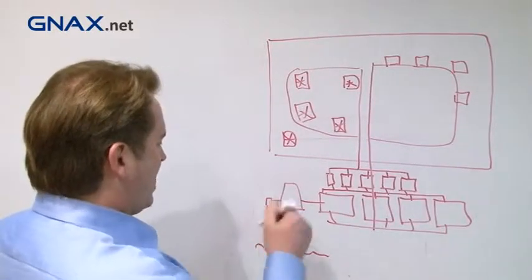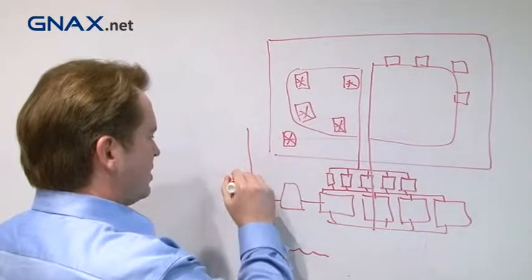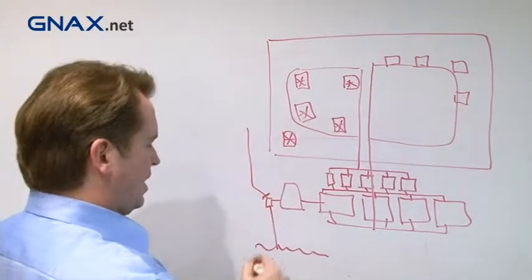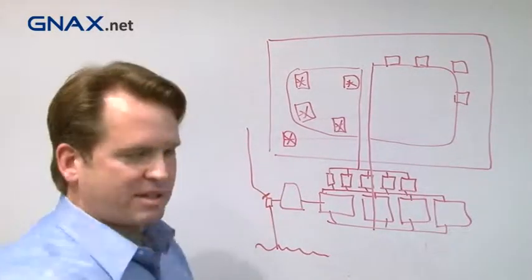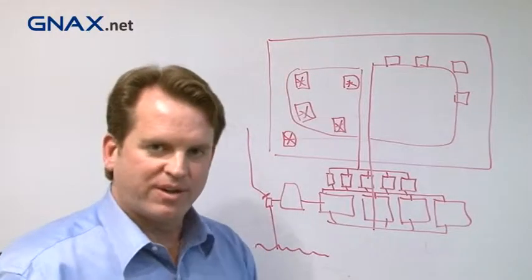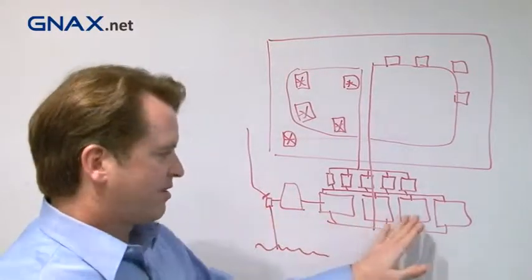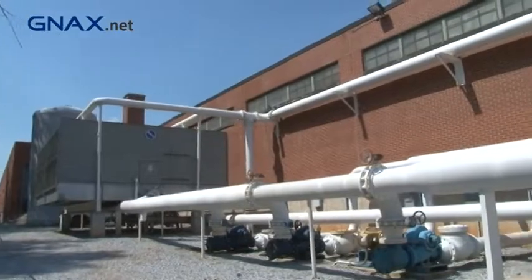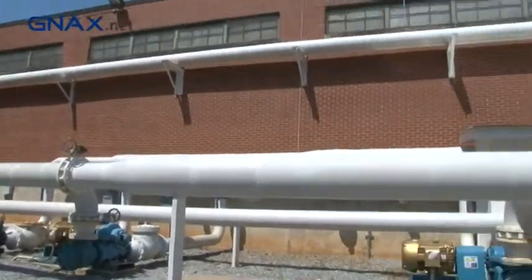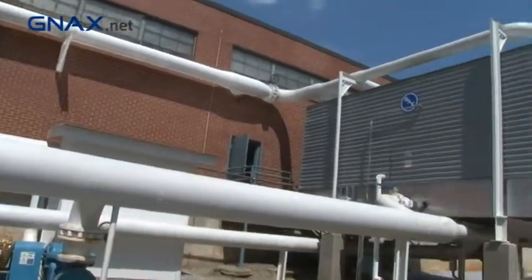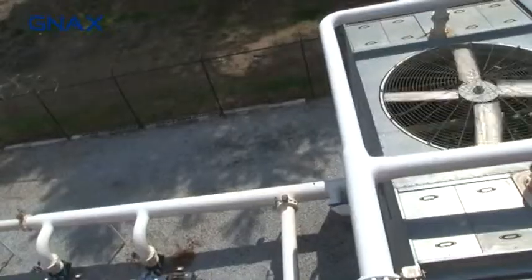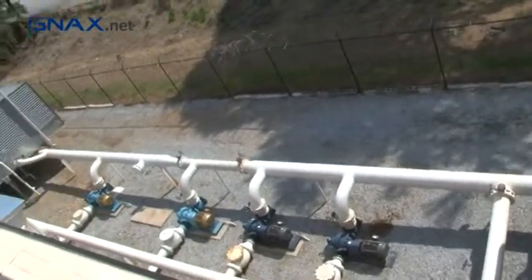We have a backup tap to the city water that allows us, with manual intervention, to go back to city water if we ever lost our well feed. This then feeds our 4 cooling towers, which are parallel N+1 redundant. The cooling towers then feed a common set of headers and pumps, which are all N+1 redundant.